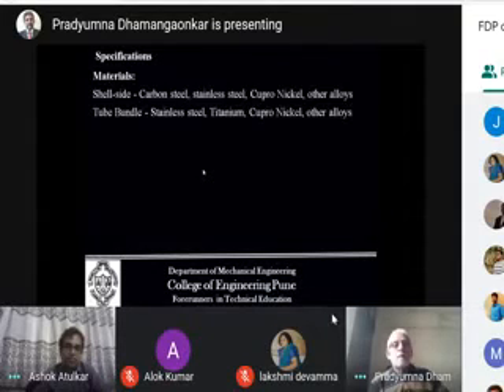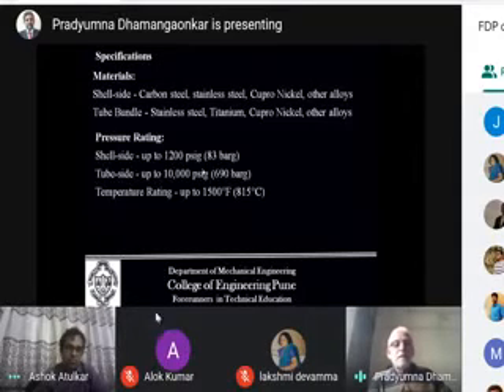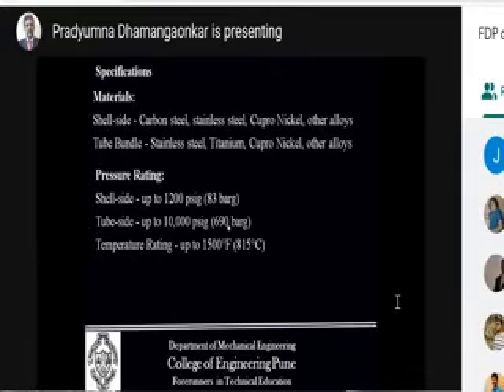We will quickly go through the specification. The shell is carbon steel. The tube bundle is stainless steel. The pressure rating is 83 gauge pressure. The tube side is nearly 690 gauge pressure. The temperature rating is very high. It is 815 degrees Celsius.